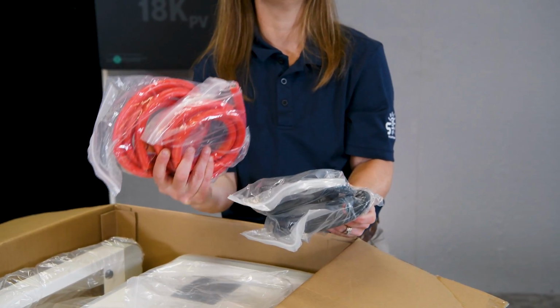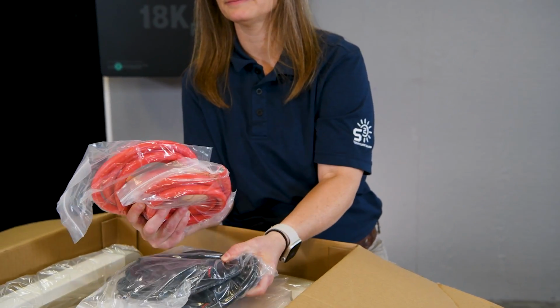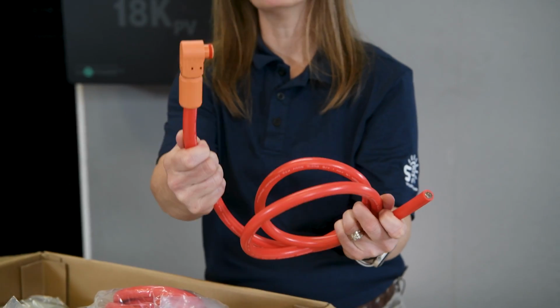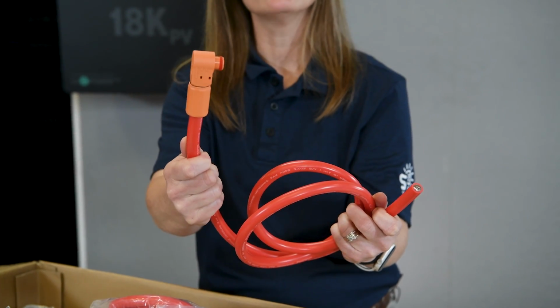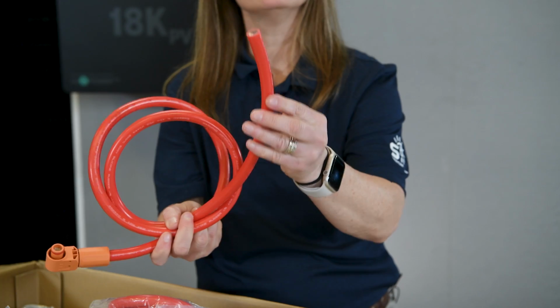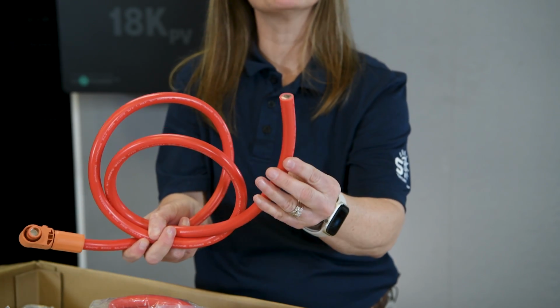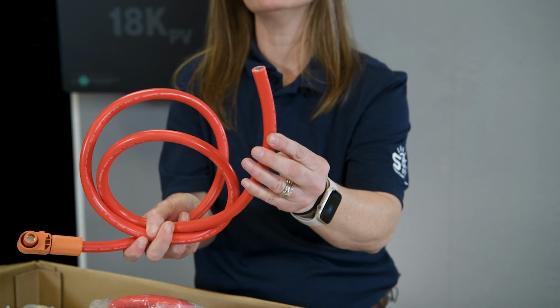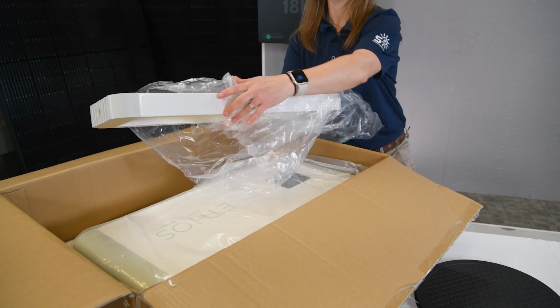Next, we have 2 sets of controller to inverter power cables for a total of 4 cables. 2 positive, the red, and 2 negative, black. We know that these go to the inverter because they have one quick connect end with the Amphenol connector and one end with just insulation that will have to be stripped to expose the bare wires to be inserted into the inverter. Here we have our battery rack base.